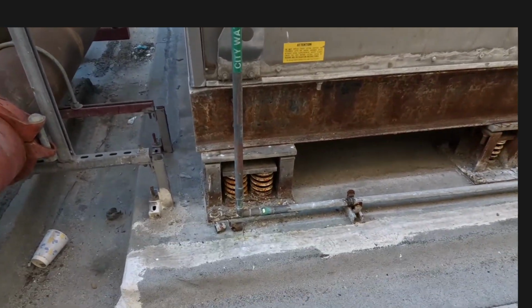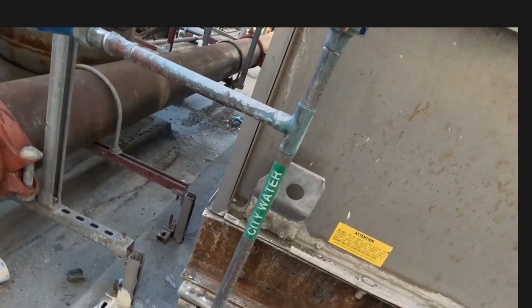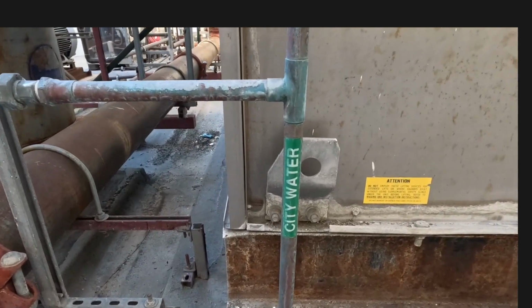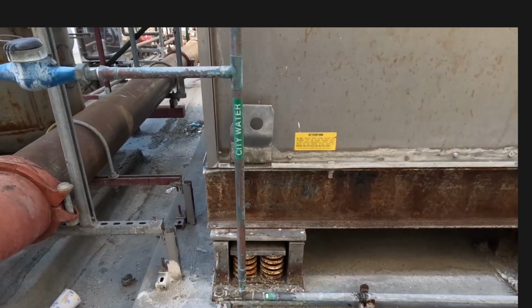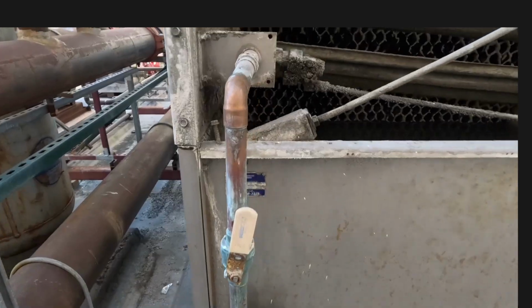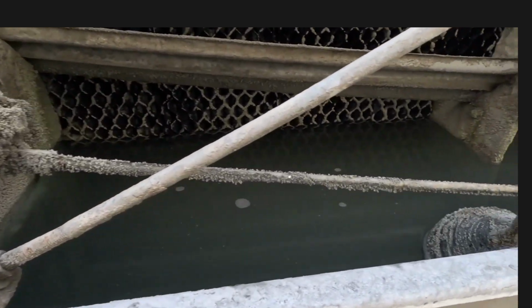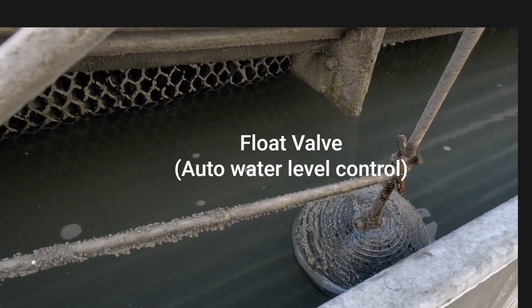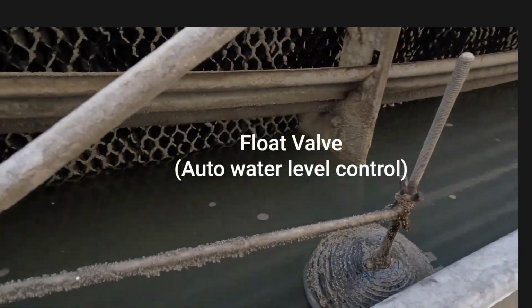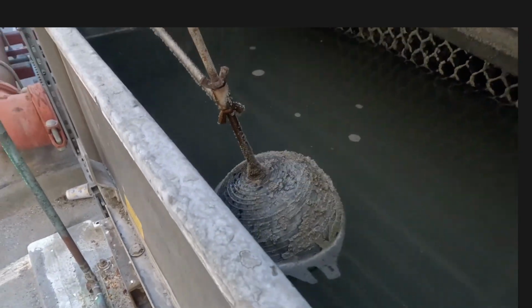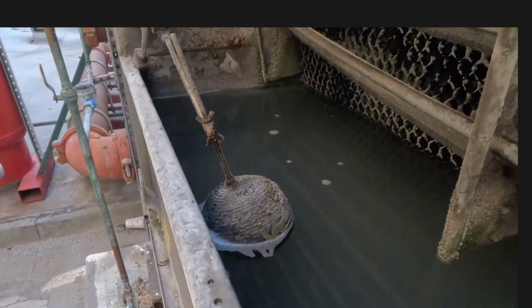This pipe right here, this is the makeup water line. You can see it's labeled city water. So this is what feeds water back into the sump here. It keeps it filled up, and it's controlled by this float valve. So this is another thing that we check on our preventative maintenance. Right? And look at the color on this water. Yeah, it needs some attention.